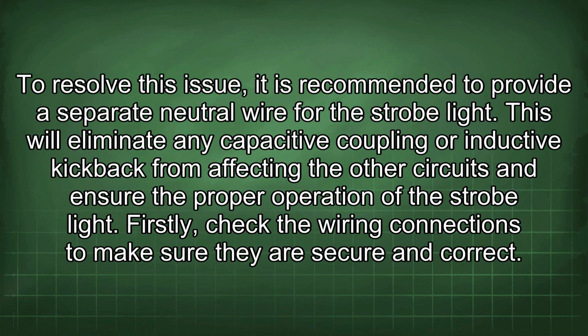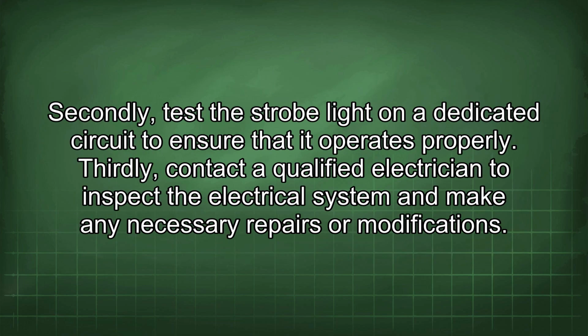To resolve this issue, it is recommended to provide a separate neutral wire for the strobe light. This will eliminate any capacitive coupling or inductive kickback from affecting the other circuits and ensure the proper operation of the strobe light. Firstly, check the wiring connections to make sure they are secure and correct. Secondly, test the strobe light on a dedicated circuit to ensure that it operates properly. Thirdly, contact a qualified electrician to inspect the electrical system and make any necessary repairs or modifications.